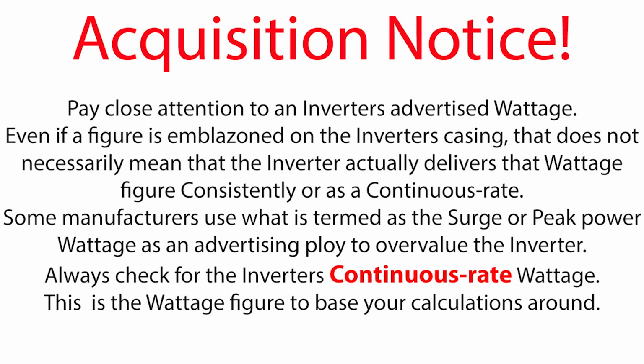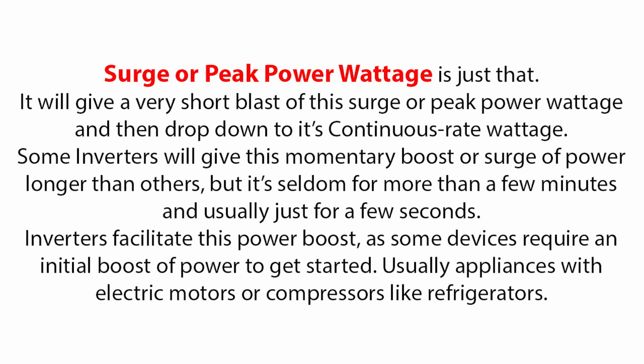Surge wattage, or the peak power wattage, is the absolute maximum power that an inverter can supply, but only for a short time, like a few seconds. However, on some models it can be as much as a few minutes or so. Also, the surge or the peak power wattage can be at a rate that might even be more than double the inverter's realistic continuous rate, so be mindful of these figures. All inverters will have to display somewhere their continuous rate wattage. It's the continuous rate wattage, or words to that effect, that we need to base our calculations on.